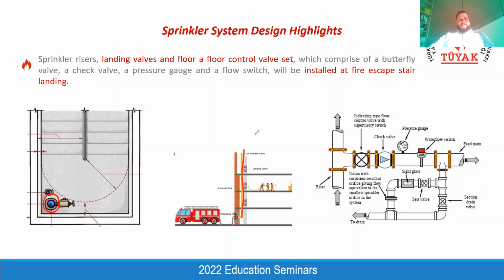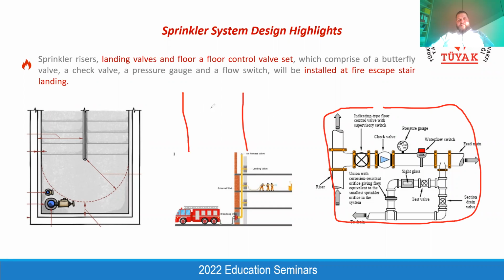It should be understood that the riser, the landing valve, and also the valve group which is provided for each floor shall be located within the staircase. We are not allowed to locate them within the mechanical shafts, or these gate valves are always required by architects to be located within the suspended ceiling. For example, we have an office floor, we have a suspended ceiling here. They are requiring to provide this equipment here with a cover reaching to the gate group.